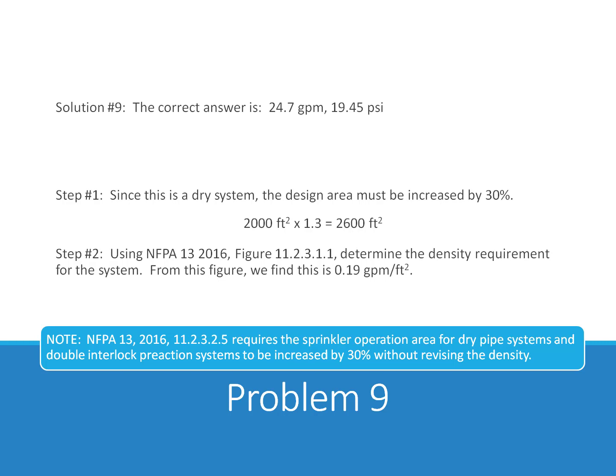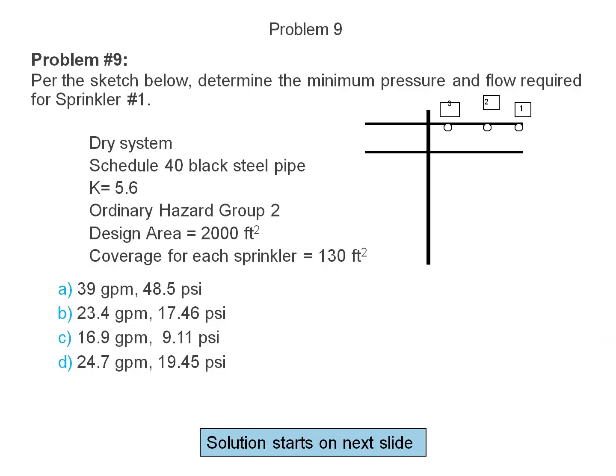Step 2. Using NFPA 13, 2016, figure 11.2.3.1.1, determine the density requirement for the system. From this figure, we find this is 0.19 gallons per minute per square foot. Per this sketch, determine the minimum pressure and flow required for sprinkler number 1.